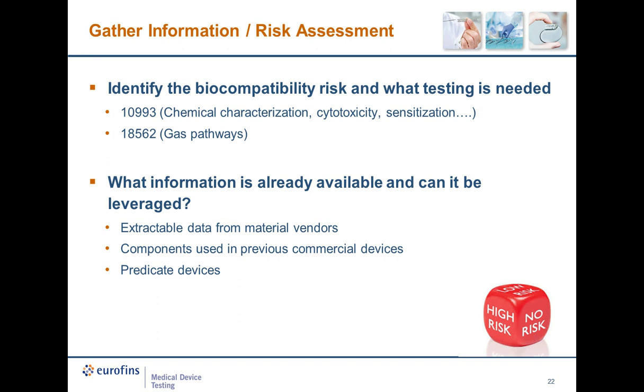Depending on the purpose of the device, ISO standards other than 10993 should also be considered. For example, a fairly new ISO standard is 18562. The Eurofins Medical Device Group has recently developed the capabilities to evaluate a device using this new standard, the purpose of which is to address the gas pathways of medical devices.